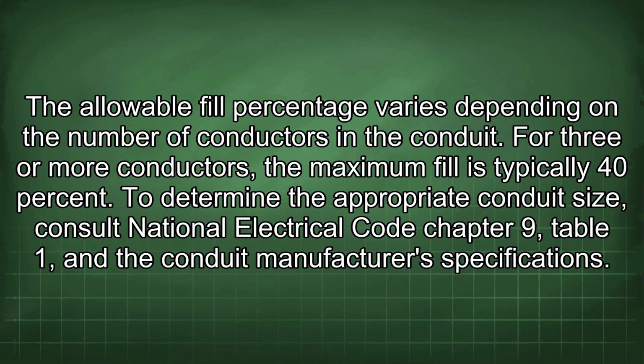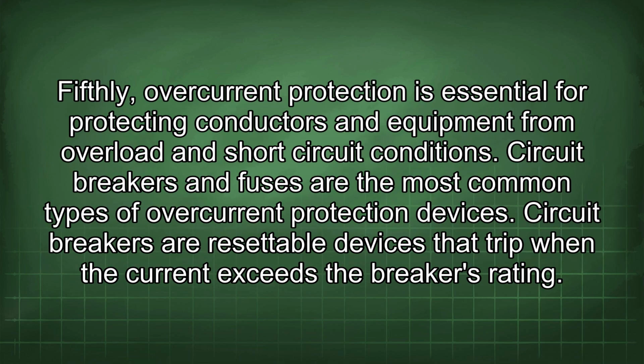The allowable fill percentage varies depending on the number of conductors in the conduit. For 3 or more conductors, the maximum fill is typically 40%. To determine the appropriate conduit size, consult National Electrical Code Chapter 9, Table 1, and the conduit manufacturer's specifications. Fifthly, overcurrent protection is essential for protecting conductors and equipment from overload and short-circuit conditions. Circuit breakers and fuses are the most common types of overcurrent protection devices.